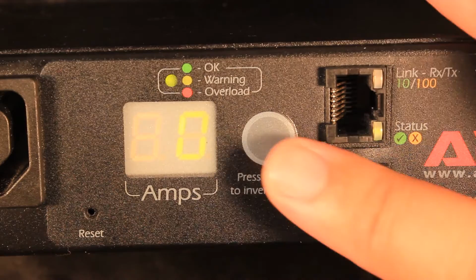Now if this power distribution unit is actively in production, don't worry, because the password reset procedure does not affect the state of the ports themselves. As you see, port number 8 and port number 7 are being powered on by the configuration on the PDU, and these should not be switched off, nor should others be switched on, during the password reset procedure. So technically speaking this should not mess up any production hardware.